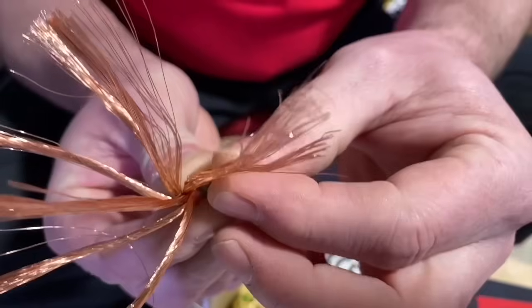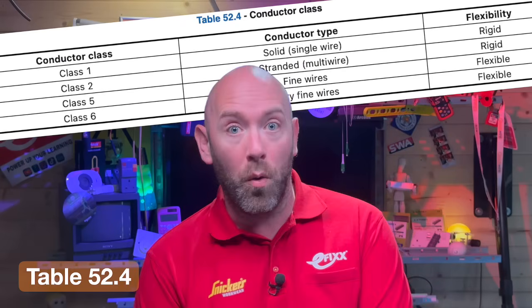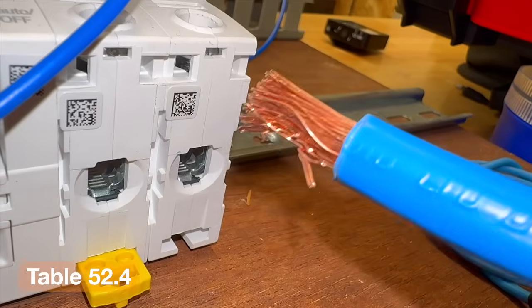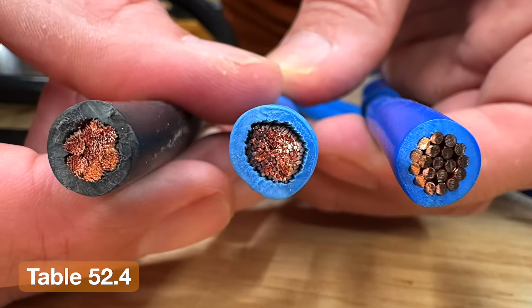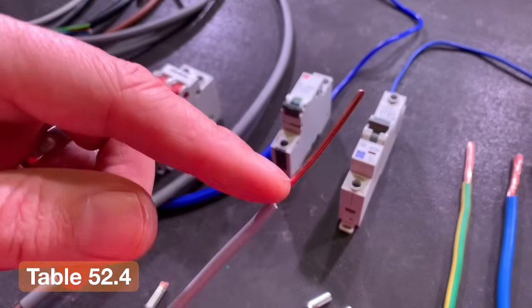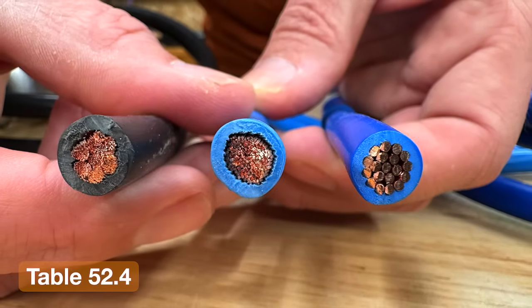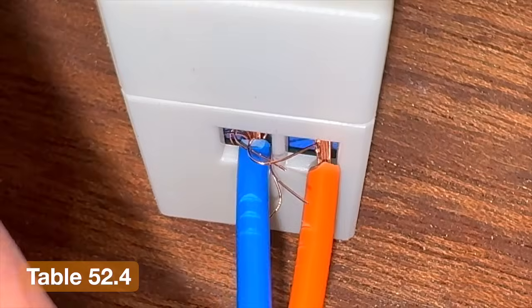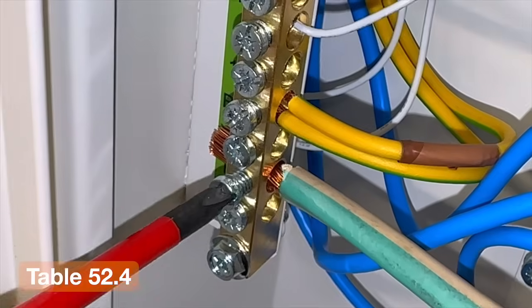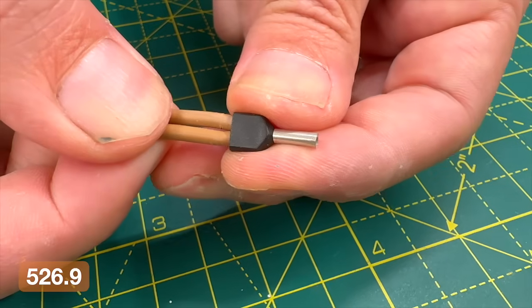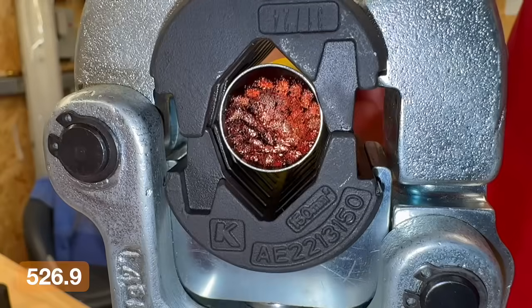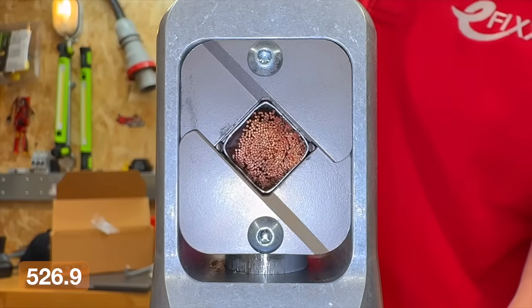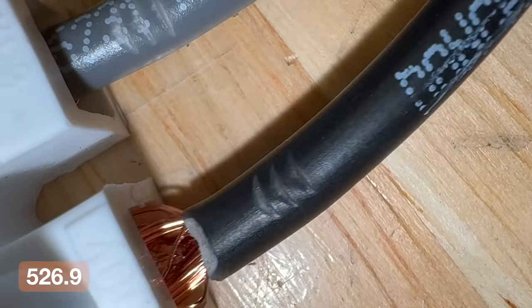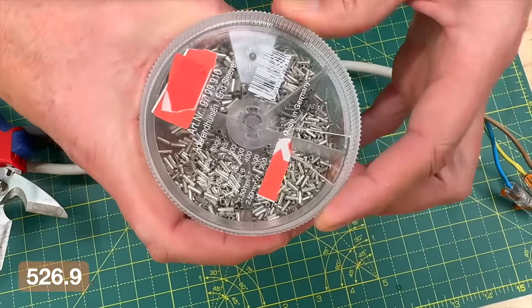There is also a new table that sets out conductor classes, Table 52.4. So instead of just referring to conductors generally, the regulations now distinguish between solid, stranded and flexible types. For example, Class 1 and Class 2 conductors are rigid, where Class 5 and Class 6 conductors are flexible. And this matters when it comes to terminations, because different conductor types behave differently when they are connected, which leads into Regulation 526.9. This focuses on the connection of multi-wire, fine wire and very fine wire conductors. If these are not terminated correctly, the strands can spread or separate, so suitable terminals must be used, or the conductor ends must be properly treated.